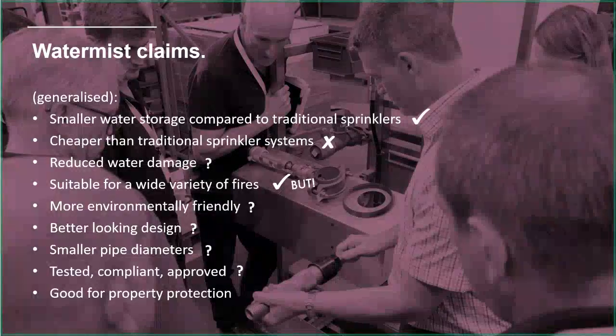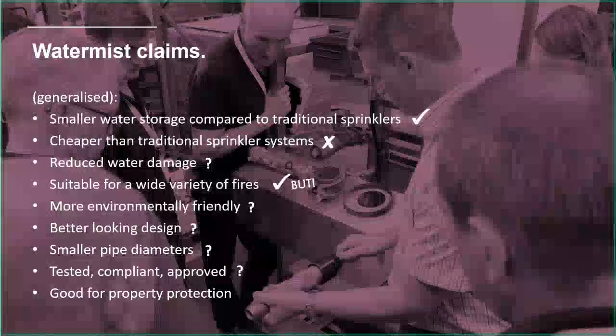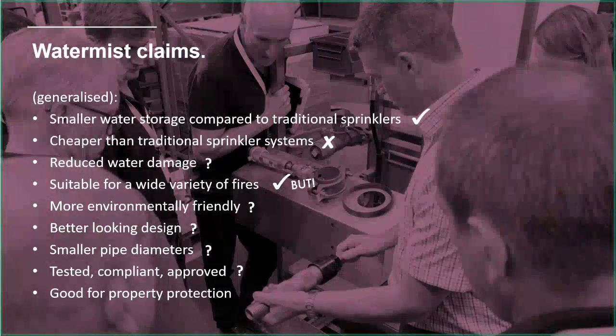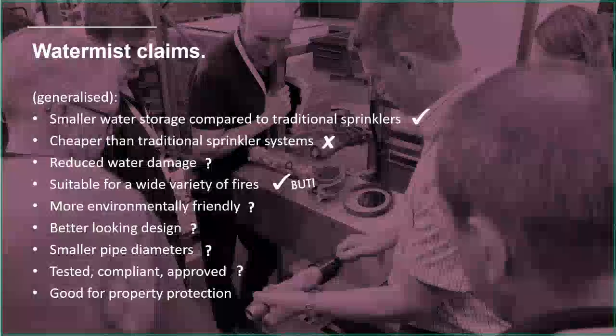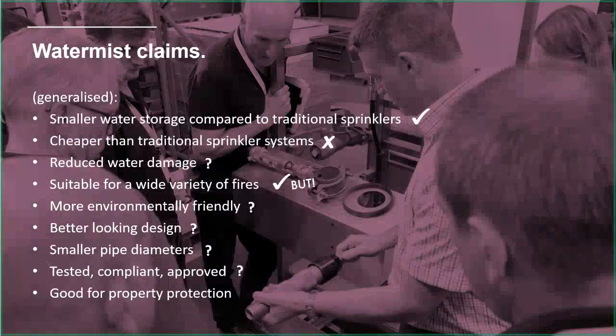What standard is it compliant to, and what evidence have they got of that? Are they basically just self-certifying their compliance, or is there a third party looking at that? Same with the approval - what exactly is it approved to? You might find that the nozzles used on the mist system are approved, but is the system approved? Is the pump approved to work with the heads? All of these questions really need to be investigated thoroughly.